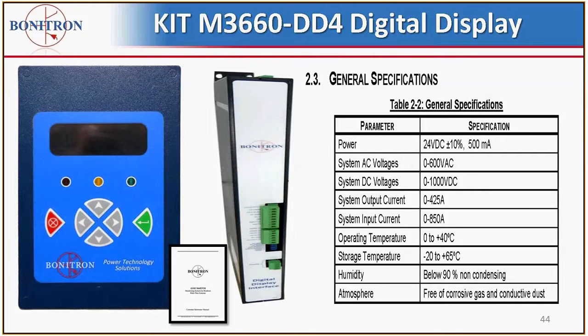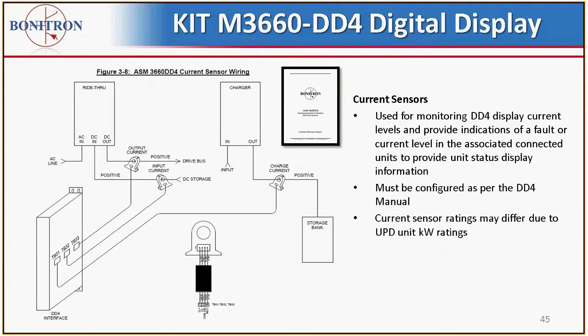This just shows specifications, and here's the current sensor networks. As you see, these are located throughout the system, and they feed the display. These are located in the DD4 manual that comes with the systems or with the DD4 display. This can also be found online on the undervoltage products page. As you can see, the current sensors monitor the DC out from the ride-through, the DC storage, and the charge current. This will feed the display to be able to give you indications of all of these different functions. Once again, all this is included in the display manual.